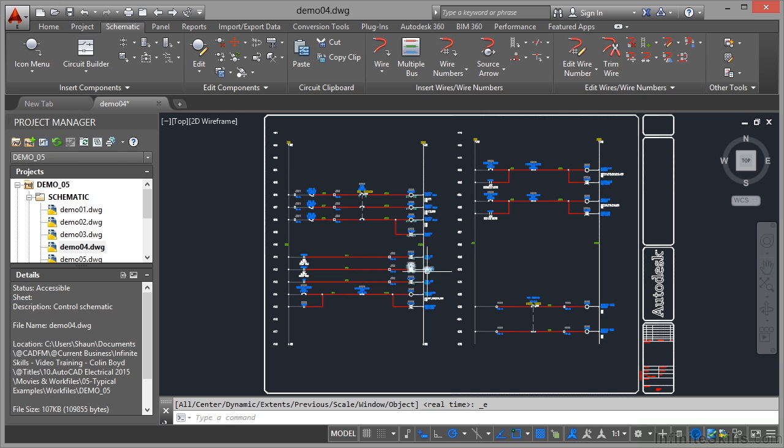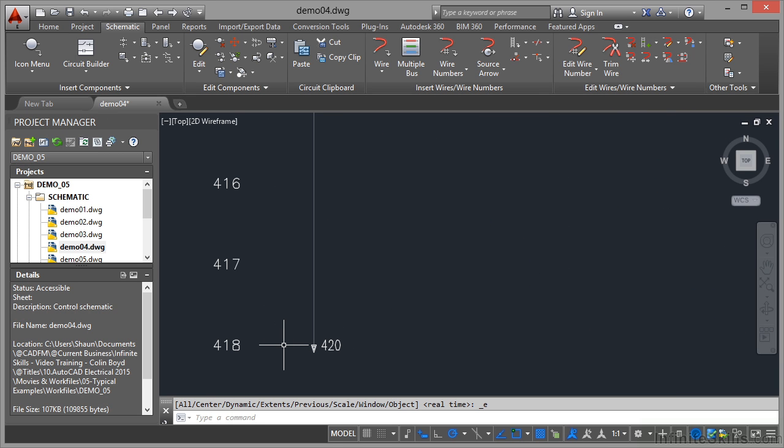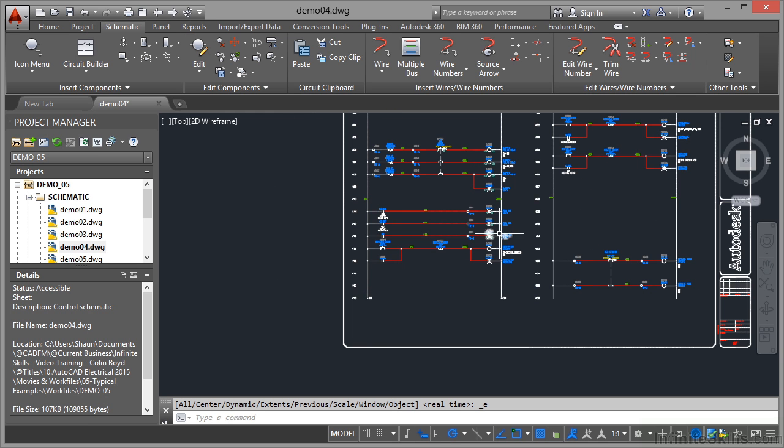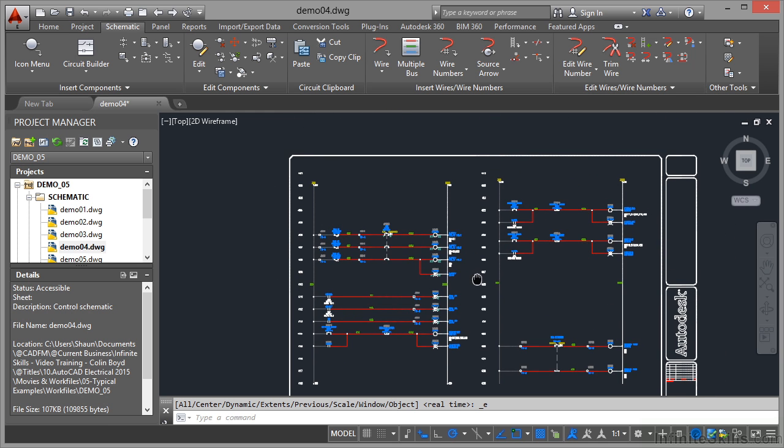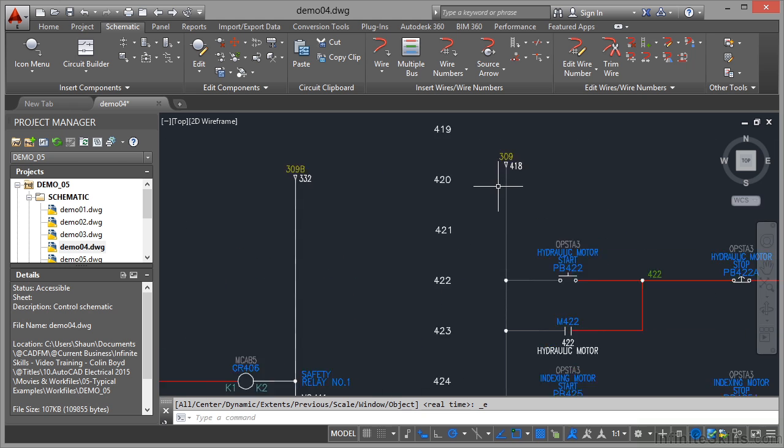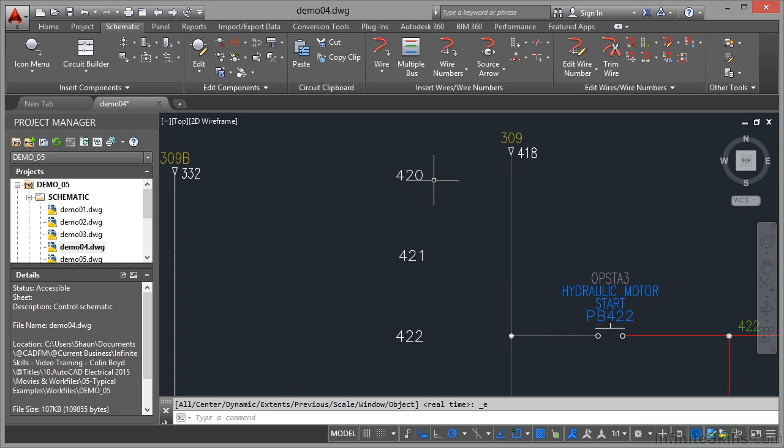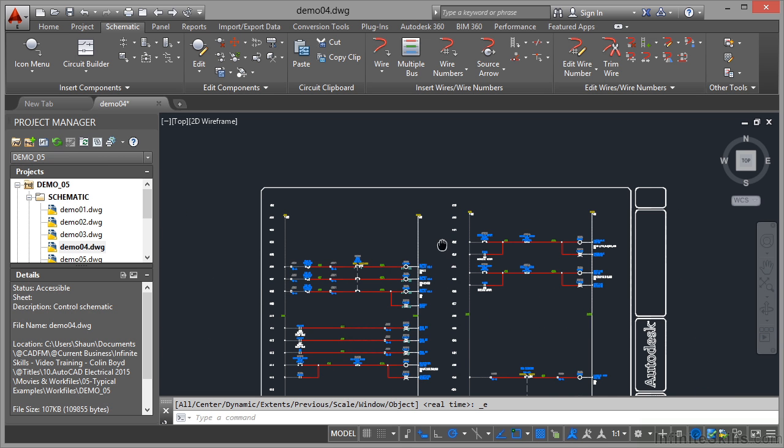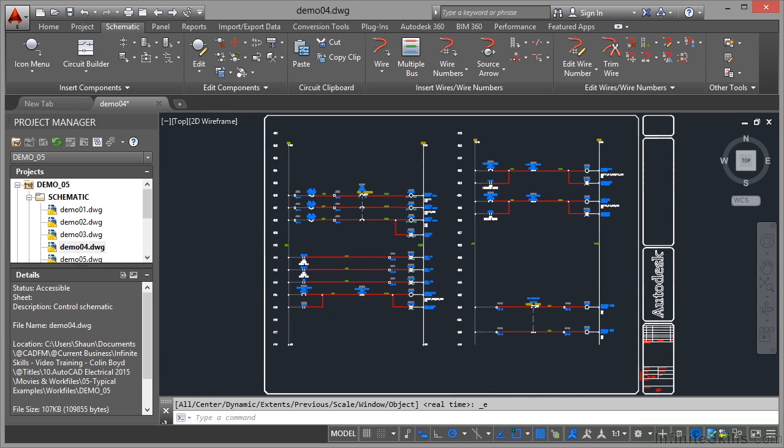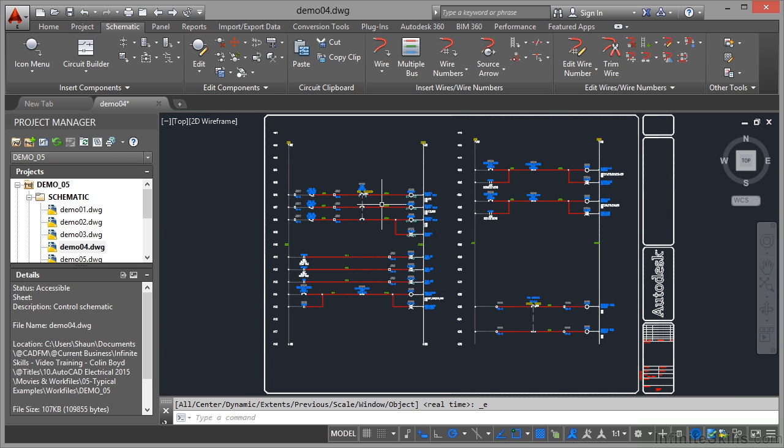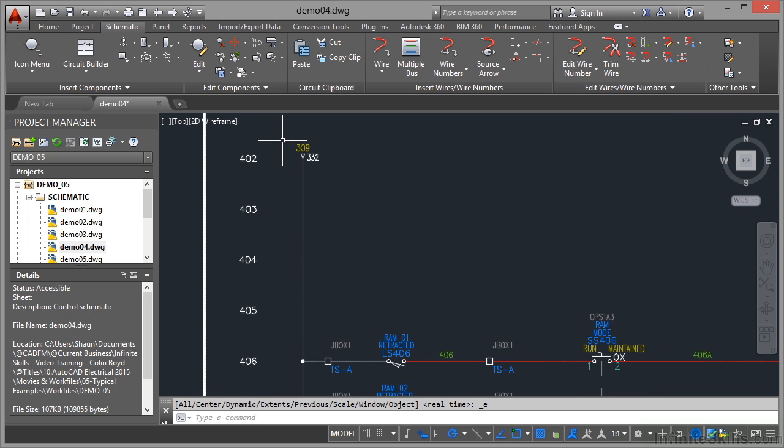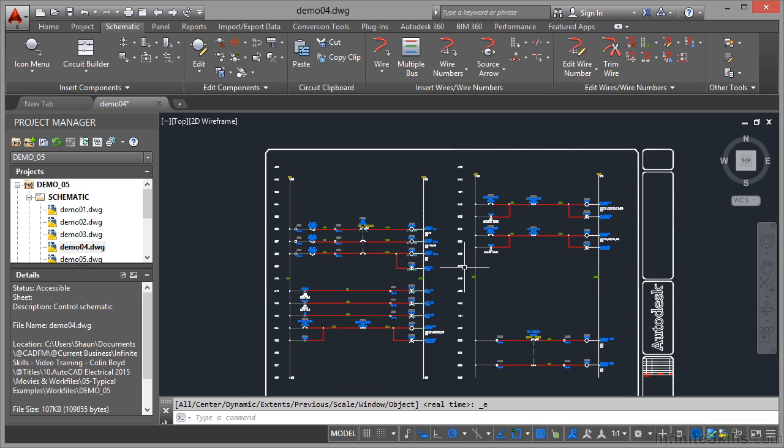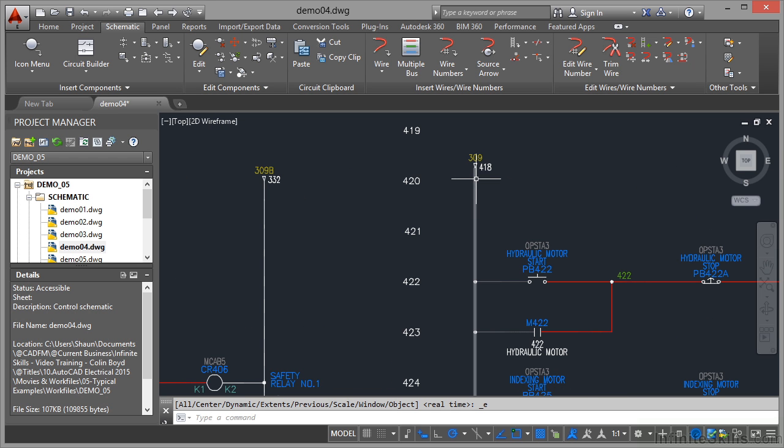You'll notice from the numbering, if I look at the bottom rung, that's at 418 and goes to 420. If I zoom out now, pan and zoom in here, there's 420 there and it tells you that it starts at 418. So what you can do is you can split the ladders as well and number them accordingly. I put one ladder in there and tell it to number from 401 right there, and then this one I'll tell it to start at 419.